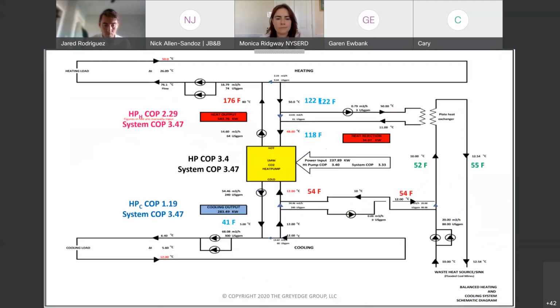This is a 6-pipe system with a CO2 heat pump generator, a new innovation that we're starting to be able to apply in the U.S. Five years ago, this wasn't available and it wasn't even UL listed in the state. But in this particular case, where we're looking at a new refrigerant and a different methodology, we're looking at retrofitting a 180°F system, what would typically be steam or high temperature hot water distribution. And we can start to look at system COPs and what's happening here with these generators.